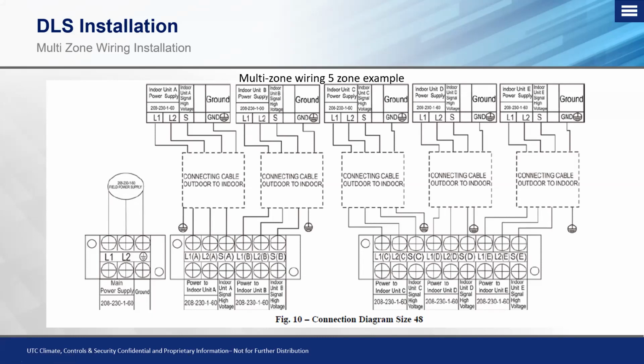And what happens is when you crisscross these lines and you go to start everything up and you fire off everything at once, if you have a zone that's crisscrossed, well, everything's getting refrigerant, so you're not going to be able to pick up on a cross line. What's going to happen is you're going to fire everything off all at once, start the system up, everything looks great in heat, everything looks great in cool.